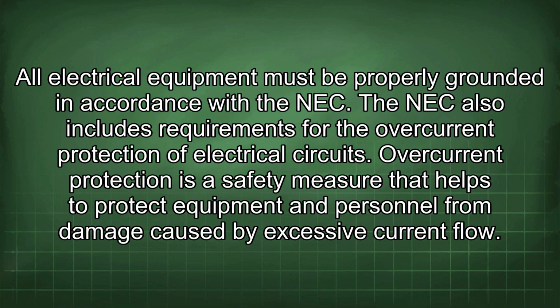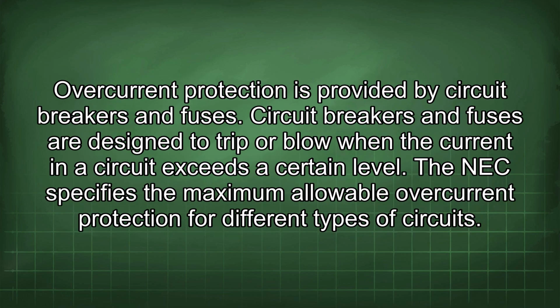The NEC also includes requirements for the overcurrent protection of electrical circuits. Overcurrent protection is a safety measure that helps to protect equipment and personnel from damage caused by excessive current flow. Overcurrent protection is provided by circuit breakers and fuses. Circuit breakers and fuses are designed to trip or blow when the current in a circuit exceeds a certain level. The NEC specifies the maximum allowable overcurrent protection for different types of circuits.